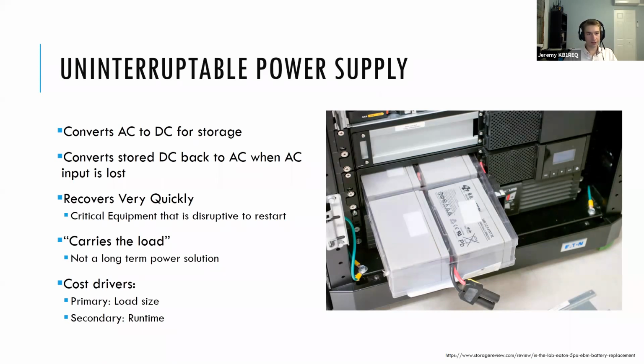The way they work on a very basic level is they have an AC input. It converts it to DC for power storage. And then when that AC input is lost and you need backup power, it automatically switches to the DC batteries, converts it back to AC, and provides that power to your devices. And so again, it's very quick recovery. So this is aimed at equipment that is, one, critical to stay operational, and that any loss of power to that device, any restart or reboot of that device is extremely disruptive.